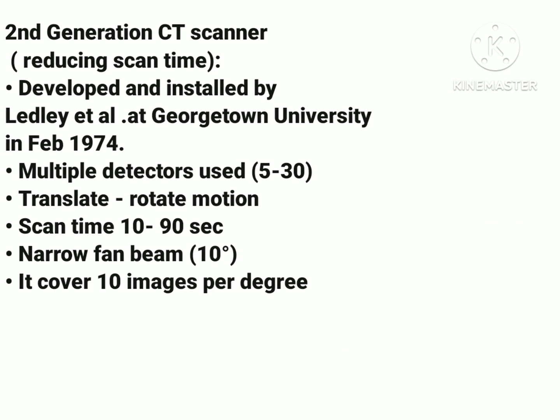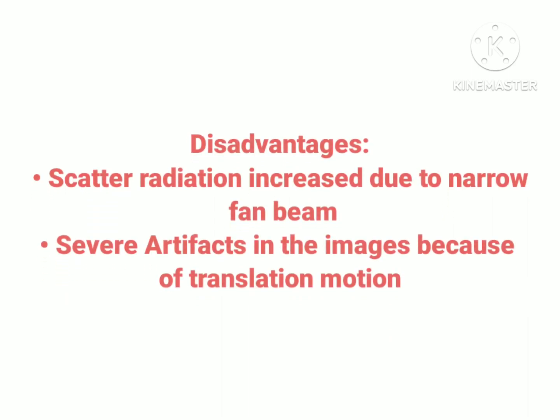Disadvantages of the second generation CT scanner: firstly, scatter radiation increased due to the narrow fan beam. Next, there were severe artifacts seen in the image because the translation and rotation needed to be performed quickly and precisely while moving heavy X-ray tubes and associated gantries and electronics. Even a small variation or deviation of the scanner hardware position related to the reconstruction matrix or voxels would cause data to be back-projected to the wrong voxels, creating severe artifacts. This indicated the need to eliminate the translation motion.